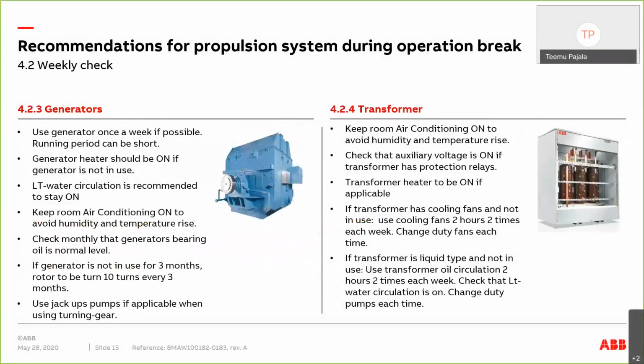And then the weekly checks continue on generators. Generators should be used regularly. It's mechanical equipment, and it's meant to be running and rotating. If there's no rotation, damage will come to the bearings, and corrosion and that kind of thing. So it's good to rotate and run the generators so that all of the generators have been used on a weekly basis. Also, LT water circulation should be on. Heaters should be on when the generator is not in use.